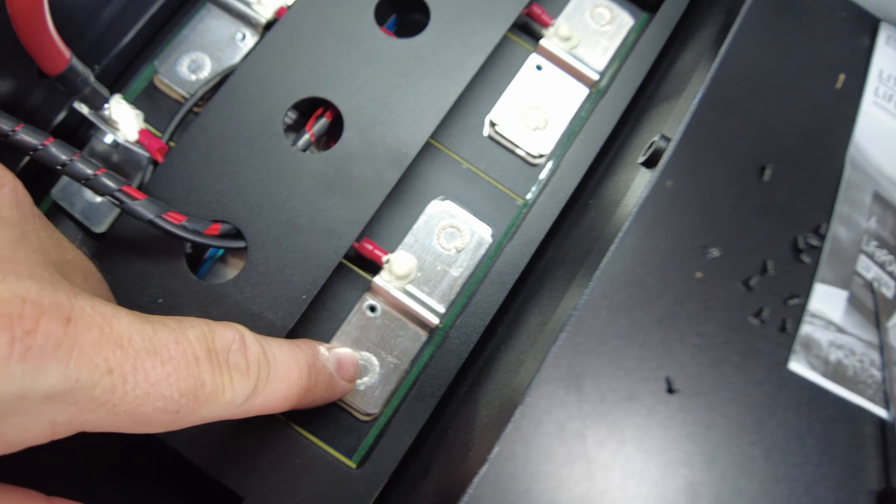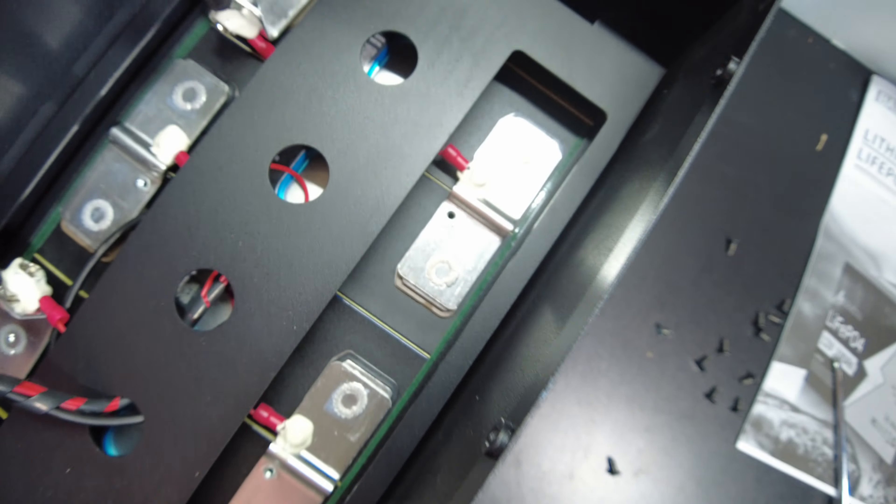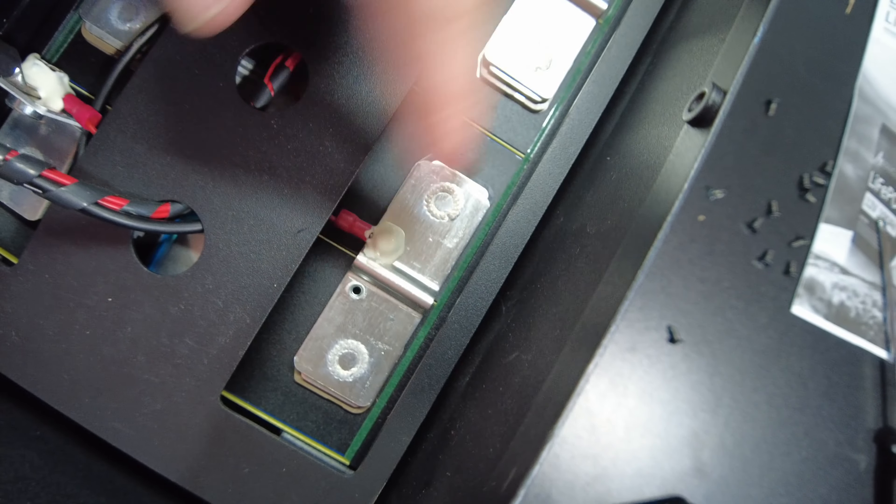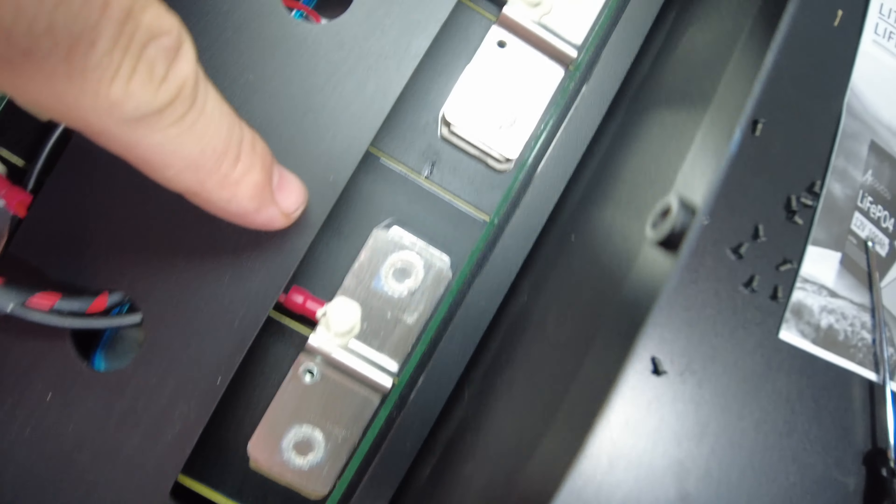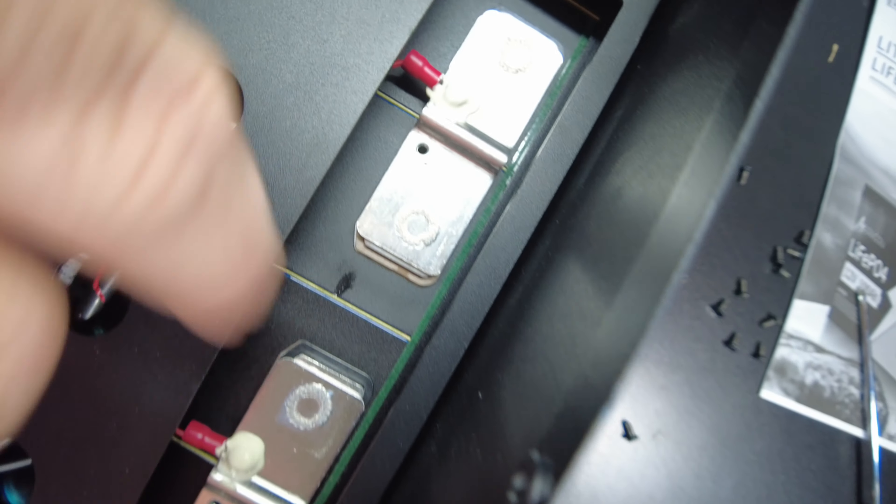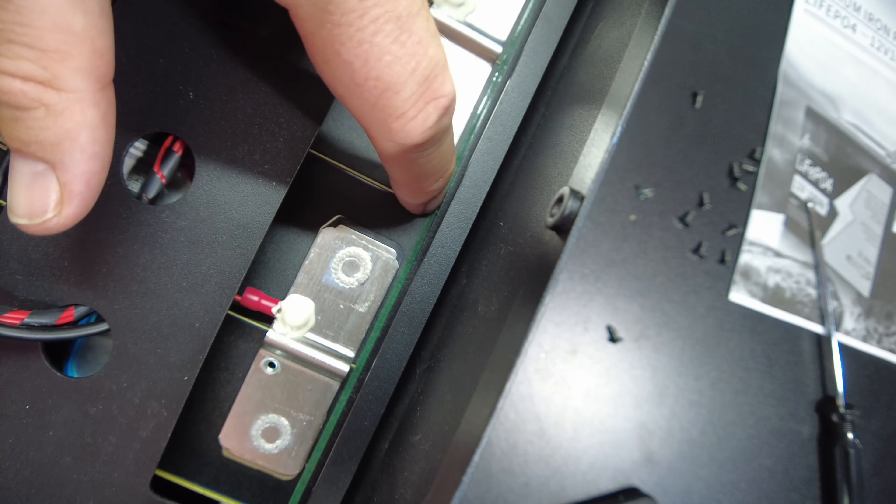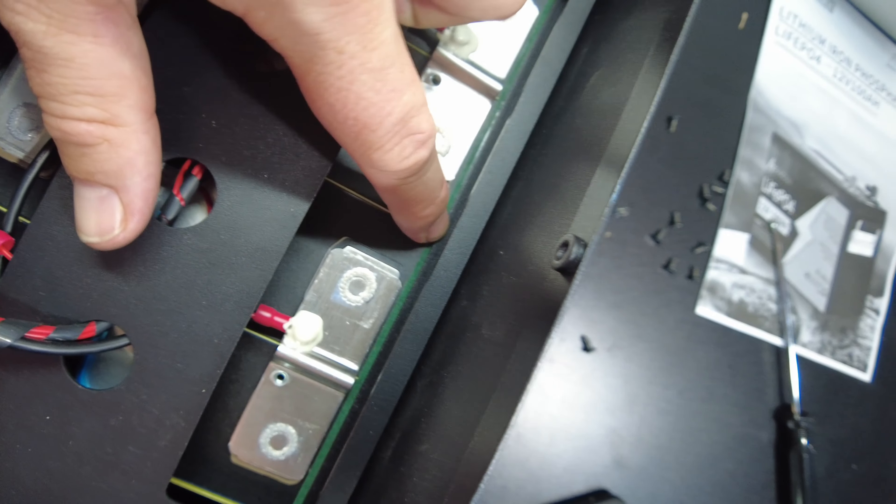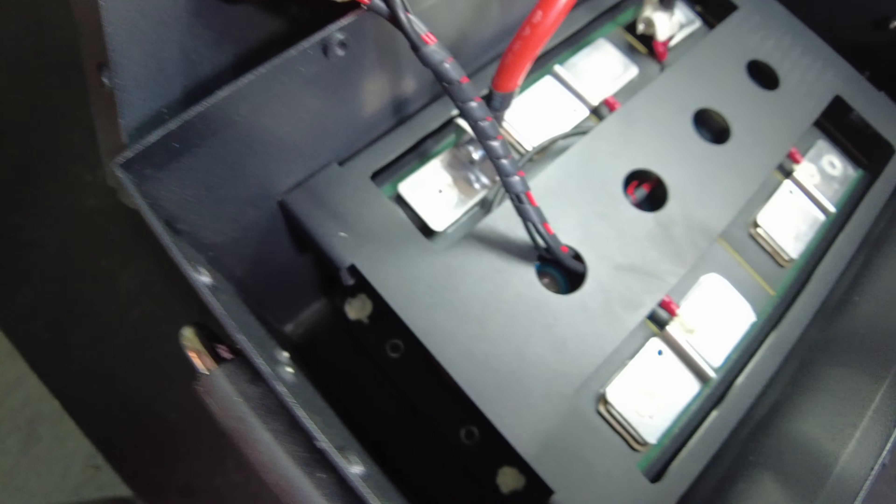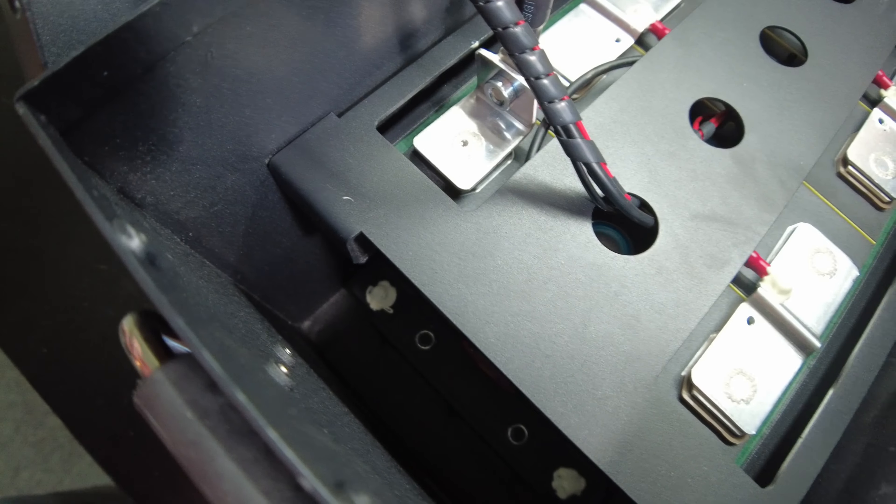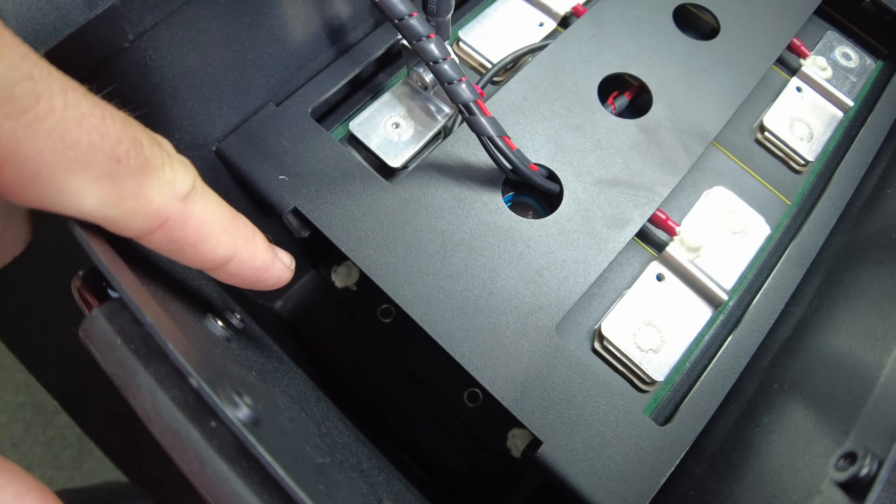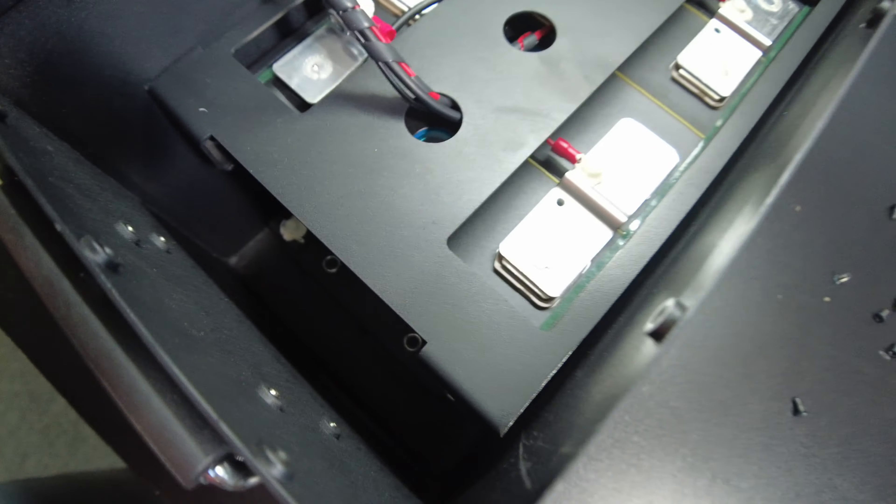And the cells have laser-welded aluminum bus bars. I can see that there is a fiberboard insulator between each cell here. And then there's insulation on the sides of the cells where it contacts this metal frame. And it looks like the whole metal frame is held in with some nuts at the base.